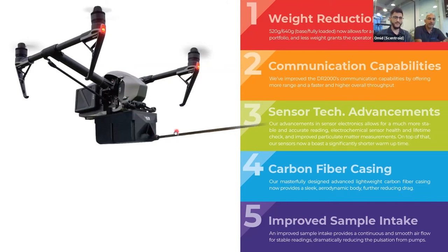So some of the advancements, as Omid was saying, through the use of the new electronic board that we have, and through the way that we deliver air to the sensor, means we can achieve things for some sensors that were not possible before in this industry. For example, we can detect methane at sub-ppm levels. Methane with a compact gas sensor was usually well over 50 or 20 ppm, but now we can get into the ppb levels for methane as well. Other sensors like H2S, SO2, and NO can detect below 10 ppb, and even ammonia can get down to ppb level detection, which was really rare. That's why it opens up a lot of new applications, which we'll talk about, like electronic manufacturing, wafer manufacturing, or leak detection because of these new advancements.